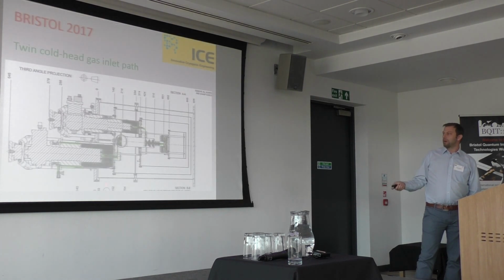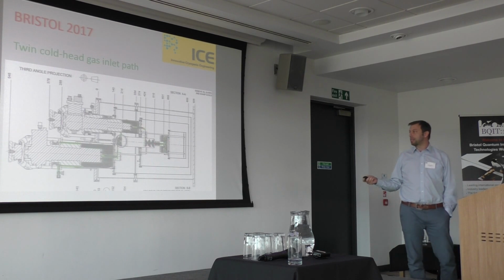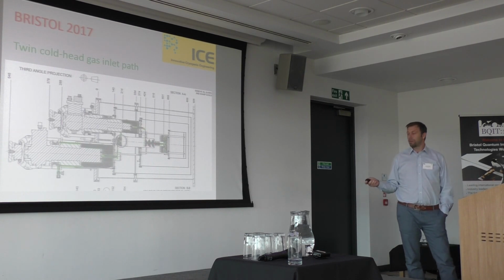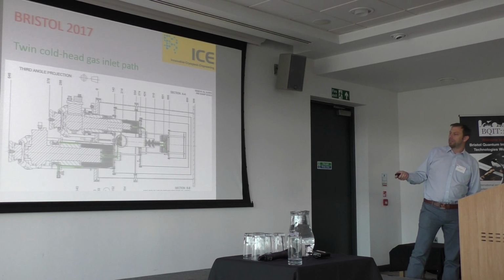What we had to do a huge amount of work on was the heat exchange and flow paths, to get that room temperature helium-4 gas back into the system as quickly as possible. Previously you would just feed it directly in via a single heat exchanger at the bottom of the 4K cold head; now we're feeding it into a first heat exchanger on the single stage, high cooling power cold head.